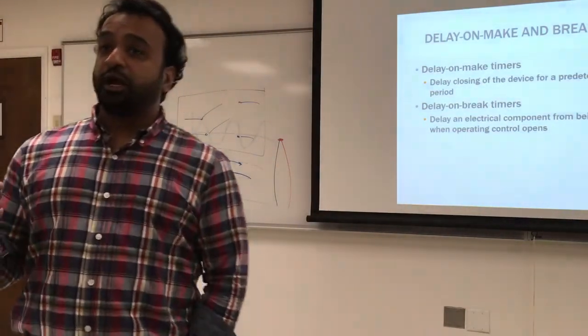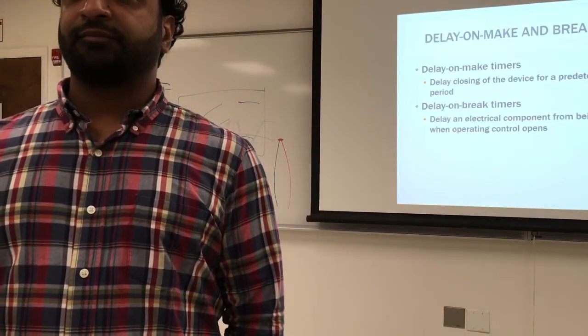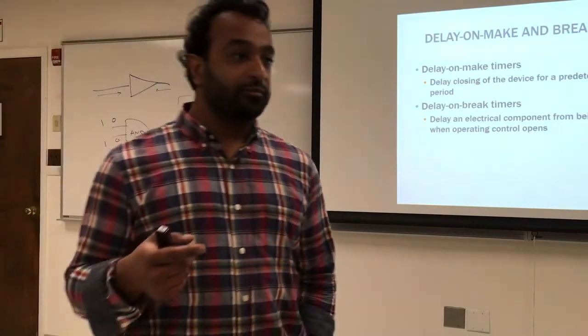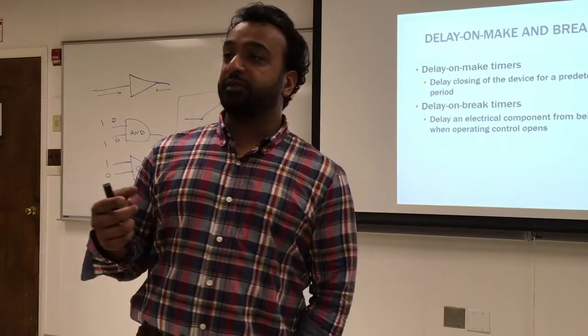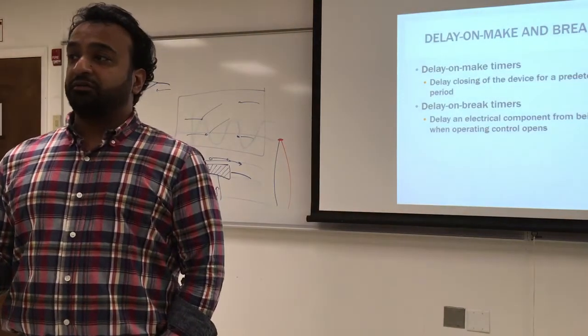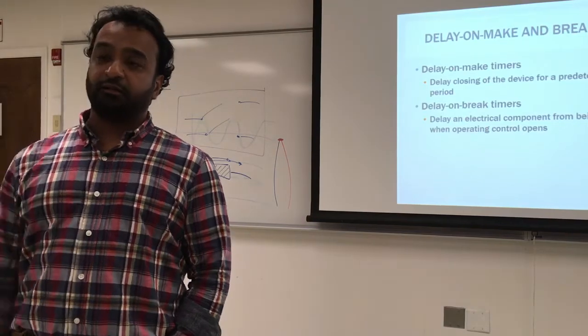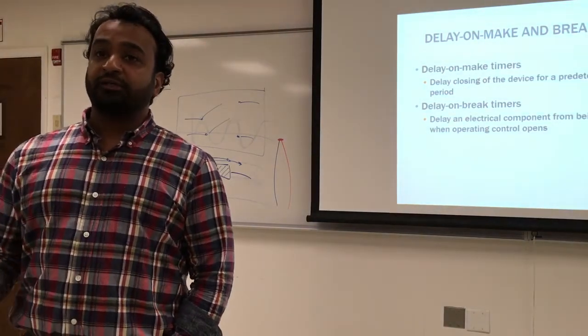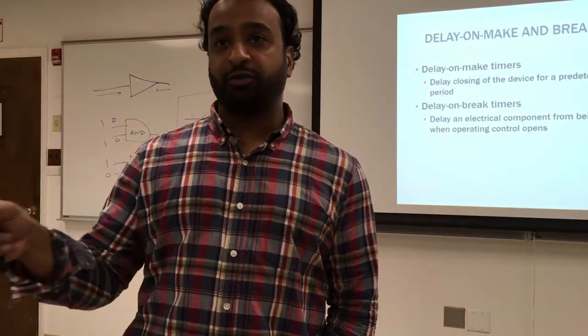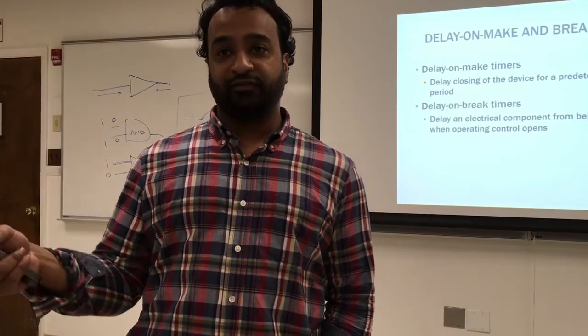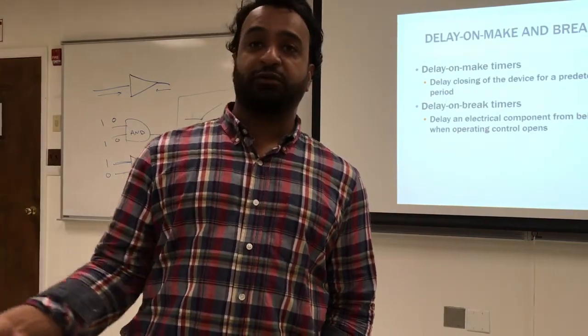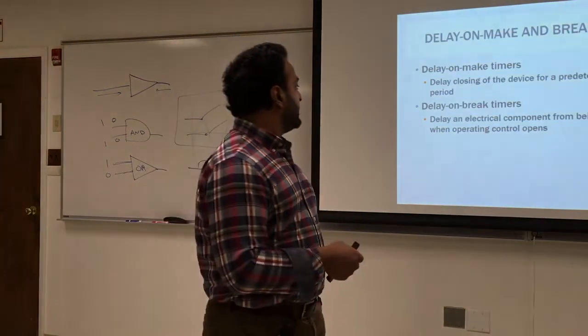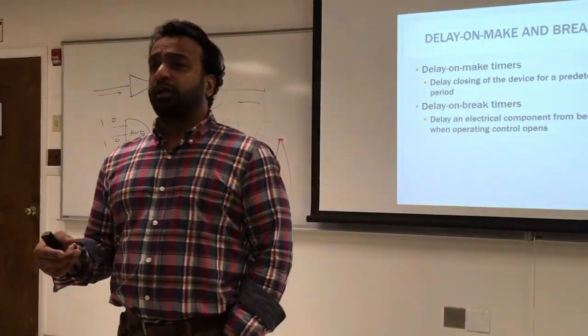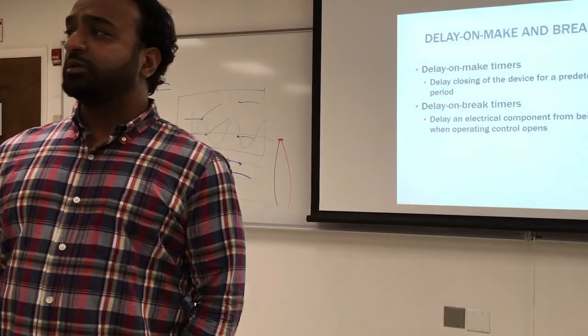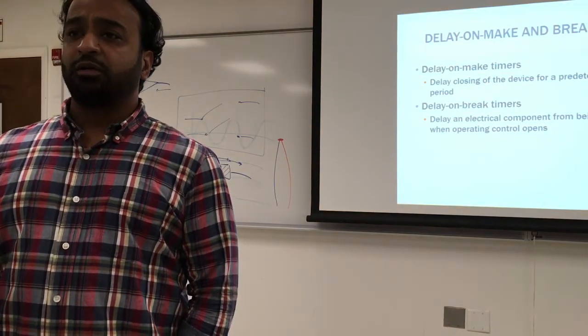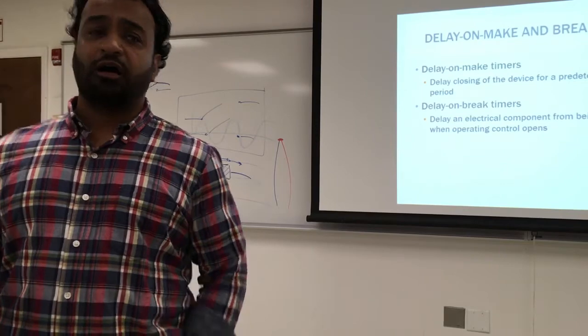For these ones, you can recycle three times. The first time you try for ignition and nothing happens, it will go on safety. You can hit the button and it will try again, and sometimes it will try by itself in 30 seconds. It will tell you there's a delay of 30 seconds, 45 seconds, or 2 minutes. That's what you're changing over here. After three times, it will go on something called a safety lockout, also known as the hard lockout.